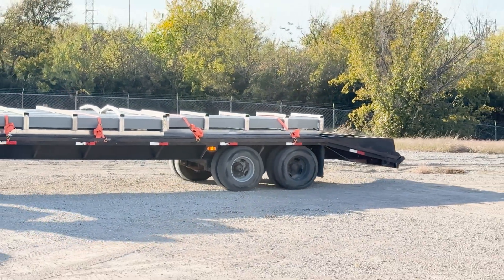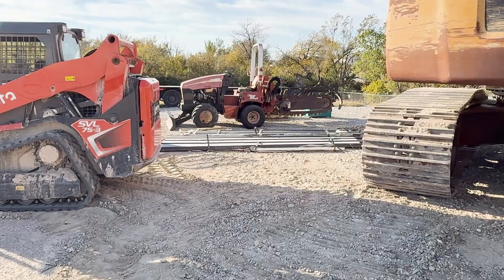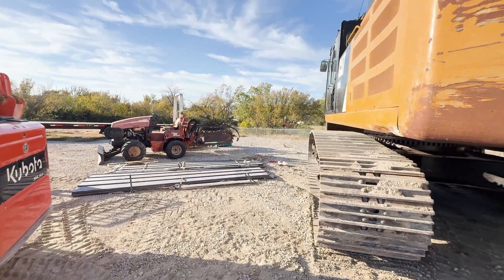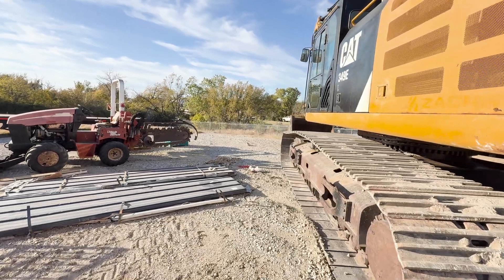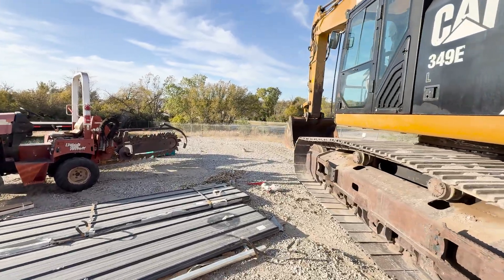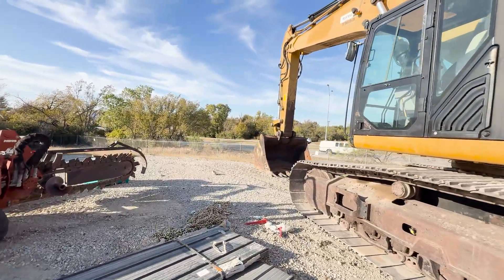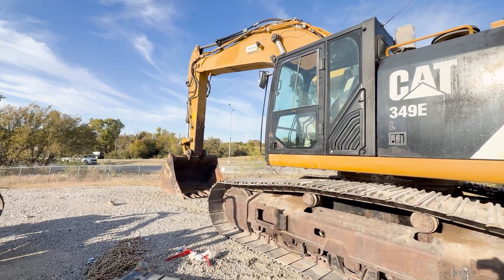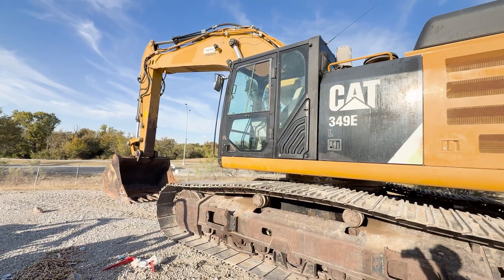A lot of people out here, I barely found parking — it's really full. Anyway, so what we plan on doing for our stranded gas site in Texas: the way we are setting that one up is we're going to be running three cabinets rather than two cabinets. The reason for that is because finding gen sets that are like 500kW and above, continuously loaded at 500kW, is practically impossible to get EPA certified.